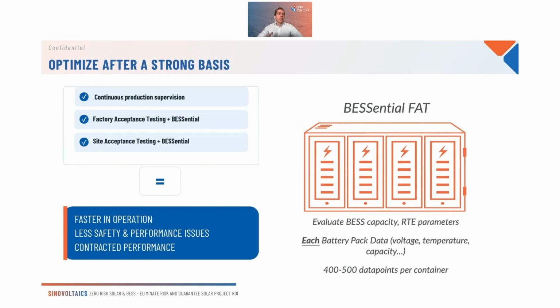So that's the first step that we do. Secondly, the normal way is also to do factory acceptance testing. For example, for batteries, you do visual inspection, safety, electrical, mechanical testing, and also a performance test, meaning a full charge-discharge cycle to see if the battery container is fulfilling its contractual performance, like energy capacity, round-trip efficiency, power, and so on.